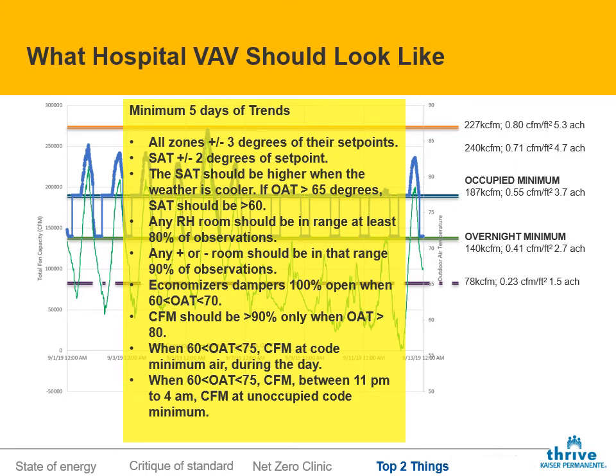Relative humidity: if there's a room that has a code required relative humidity range, put a relative humidity sensor in that room, and you should be within the range for 80% of observations. We can argue about that because that's a much broader criteria, by the way, than plus or minus 3. But that's the way that we track it. Obviously, any room that has a pressure requirement, you should put a pressure sensor in that room, and it should be within pressure range for 90% of observations. Actually, I should say any critical room with a pressure requirement, operating rooms and isolation rooms. You don't need to put pressure sensors in the clean linen storage, boys.